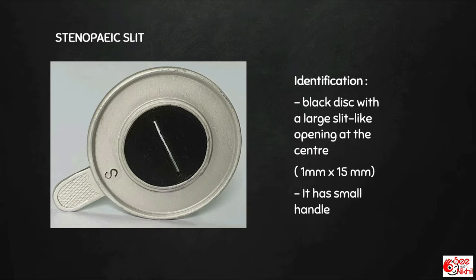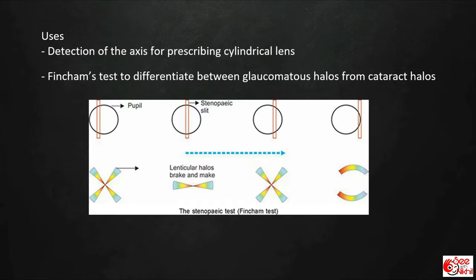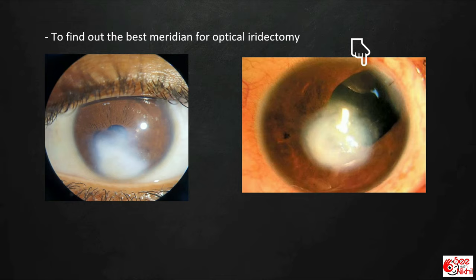This is a stenopic slit — a black disc with a slit-like opening that is 1 mm in width and 15 mm in length, with a handle. It basically acts as an elongated pinhole. It is used in detection of the axis for prescribing cylindrical lenses, in the Fincham test to differentiate glaucomatous halos from cataractous halos, and in cases where corneal opacity encroaches onto the pupillary area. Stenopic slit helps to find the best meridian for optical iridectomy. It is also used as part of the Maddox wing.